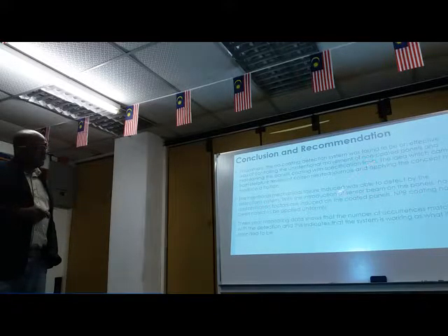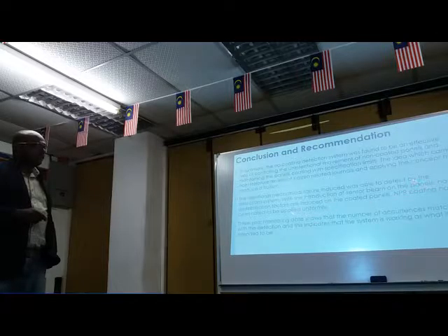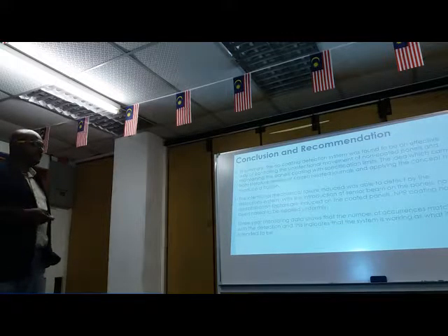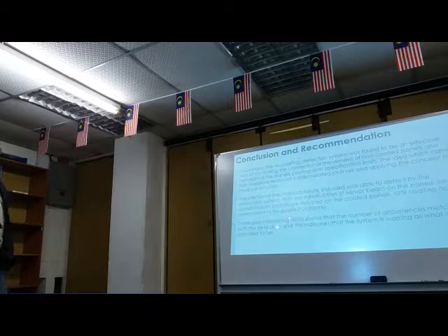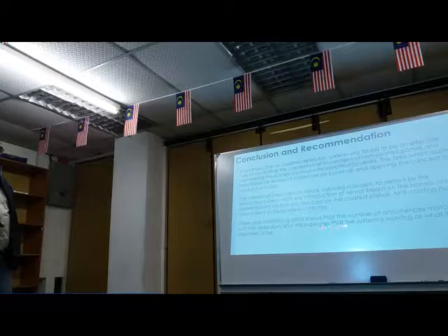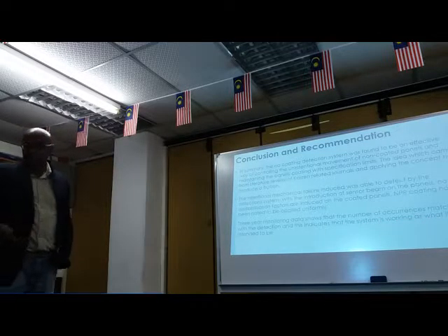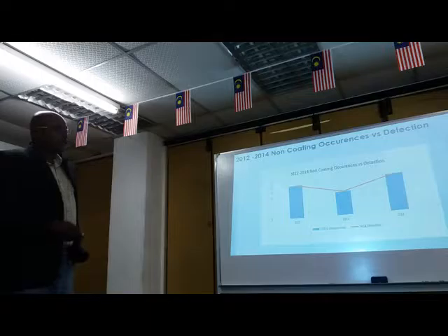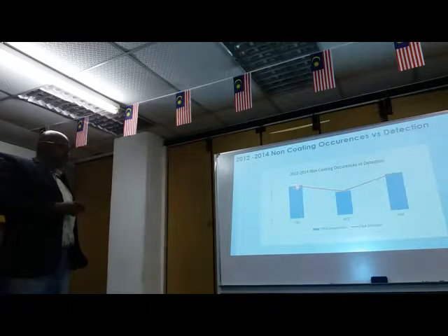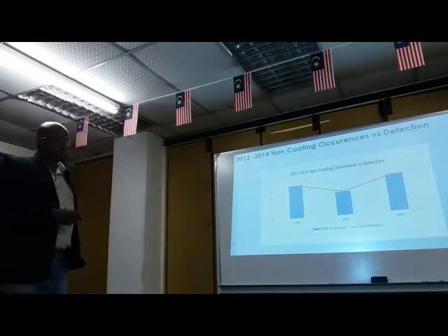Although this is a remote possibility, we always had that worry when we introduced this project. When I first came up with the idea to use the photoelectric and the fiber optic, I was worried that it could cause some destabilization factors on the panel, and it has proven that it's not the case. Three years of monitoring data shows the number of occurrences matches with the detection and indicates the system is working as intended. So in 2012 we have 6 occurrences and 6 detections. So all match accordingly.